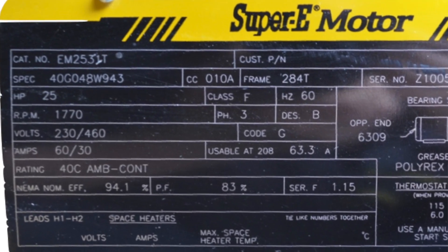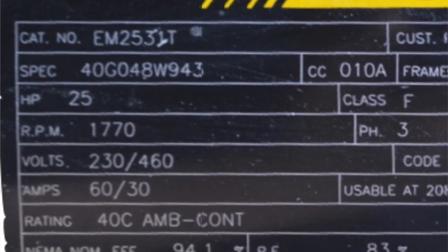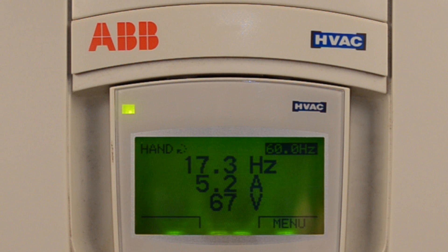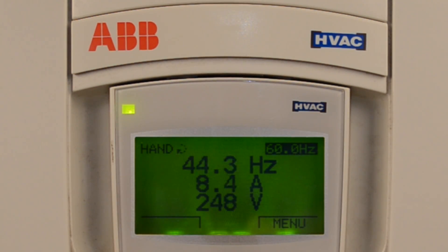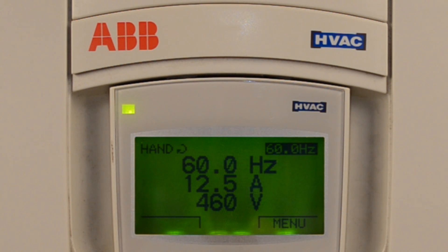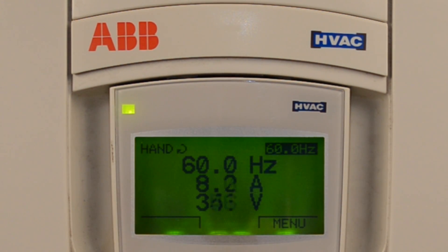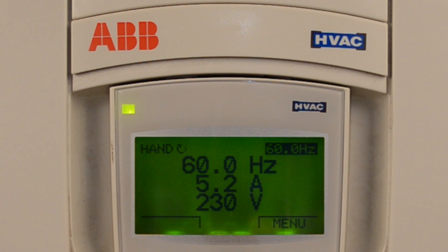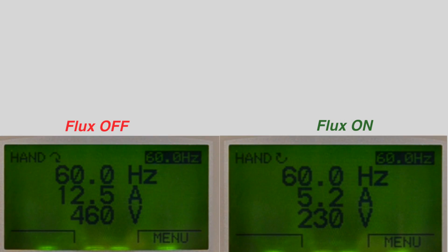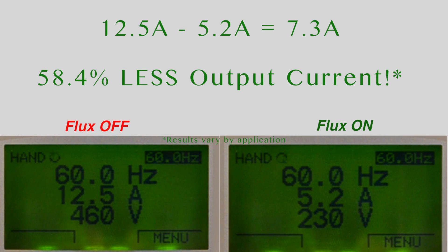Here's an example of a typical 25 horsepower, 460V motor. As we see, with flux optimization turned off, as the VFD ramps the motor to 60Hz, the output voltage goes to 460V and the output current lands at 12.5A. Now if we enable flux optimization, we can watch the voltage lower all the way down to 230V. Further, if we look at the current, it has dropped down to 5.2A. That's a 58.4% savings.